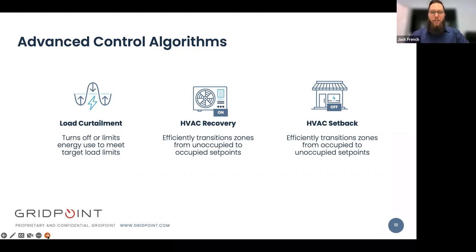This algorithm is dynamic, so it works on a 7-day rolling maximum demand. So if you're about to reach some threshold of your maximum demand within the last 7 days, this will automatically kick in and help to reduce the severity of your next peak and also operate your building efficiently and prevent unnecessary wear and tear on your units. Next two are sort of related: HVAC recovery and HVAC setback. I'll start by talking about HVAC recovery.